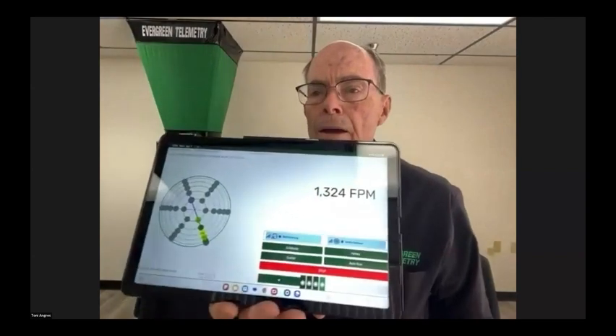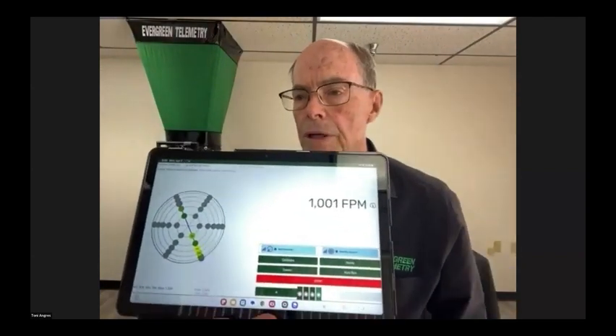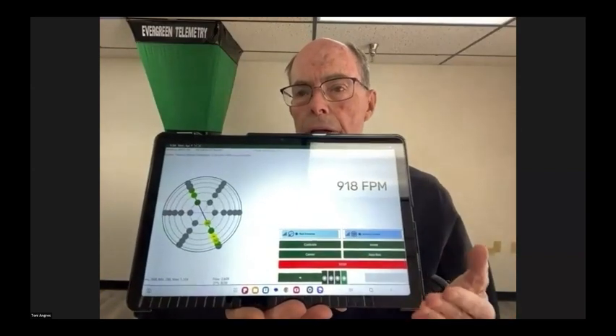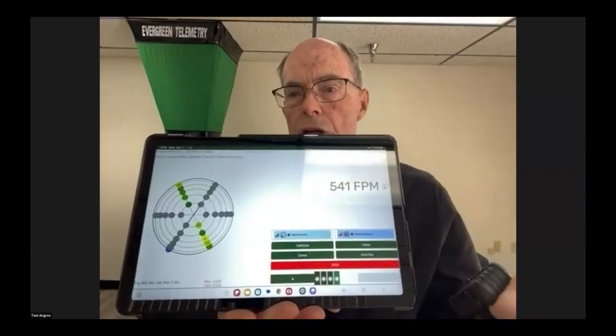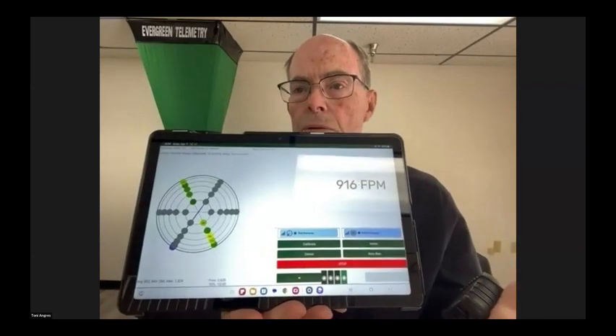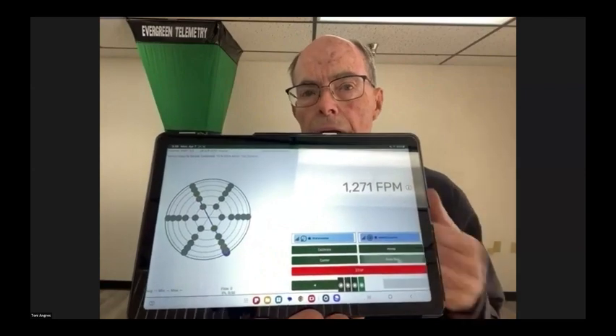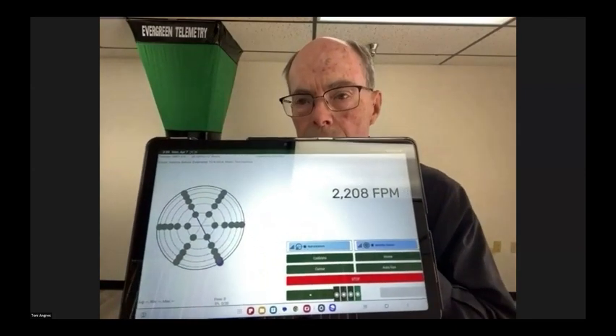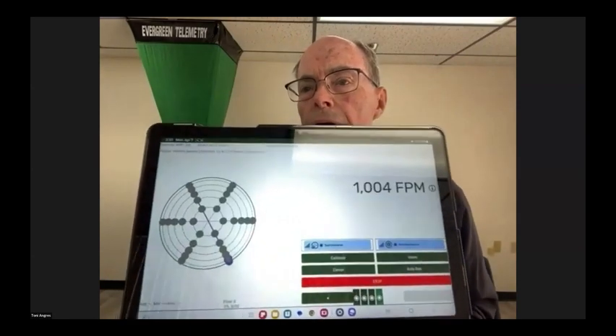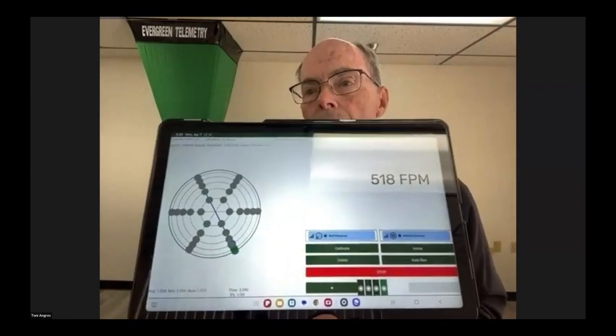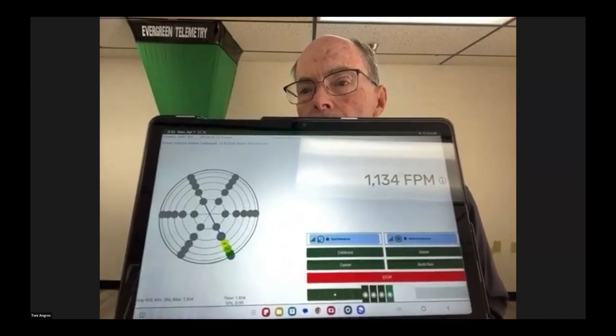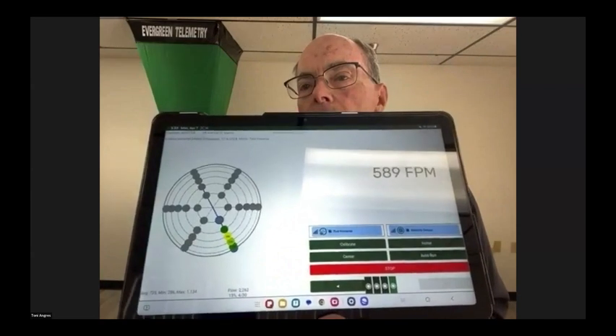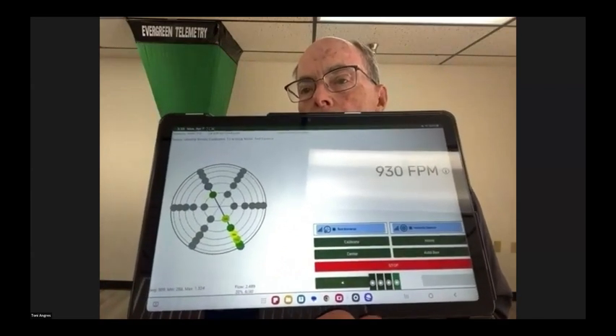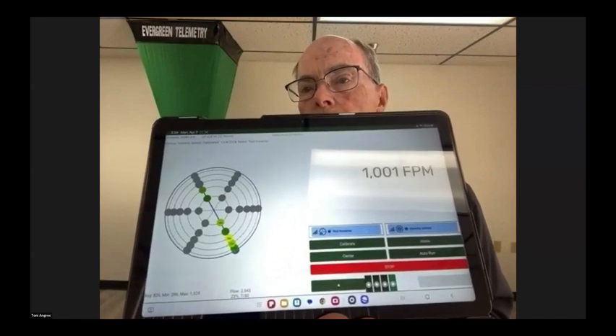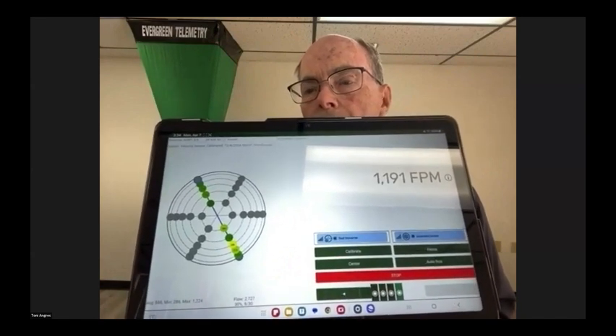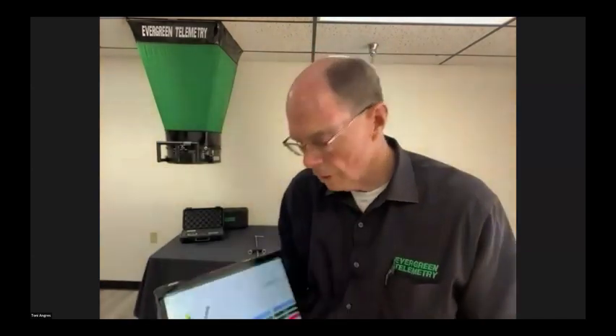This is a simulation. Before you get to this stage, you do the setup and tell the machine the size and shape of the duct, and whether you want to use equal area or log Chebyshev. Then you hit start and the machine performs the traverse for you. This is one of the many views you can select to see the progress. If you look at that diagonal, you'll see the green information coming in from a new reading, and the result in terms of average velocity and CFM will be shown.